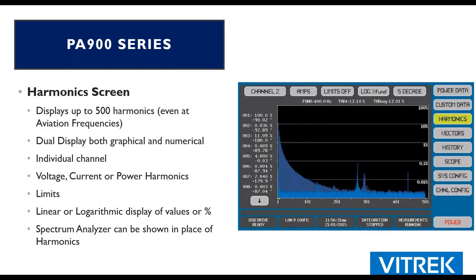Our harmonic screen is very nice and easy to use. Like I mentioned earlier, we have the ability to measure from harmonic number 1 up to 500 if need be. We get a dual display, both graphical and tabular or numerical on the left side. If you want to look at, say, harmonic number 200, on the harmonic screen in the lower left-hand corner there's a little yellow tab you can touch with your finger and slide it over to harmonic 200, and your display will give you 7 or 8 different values in that range from 200 to 207.